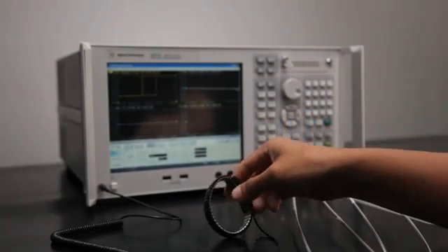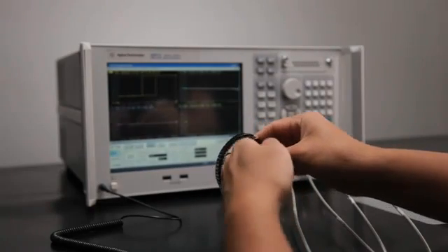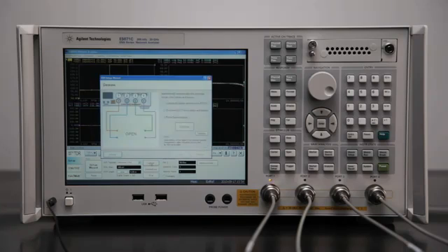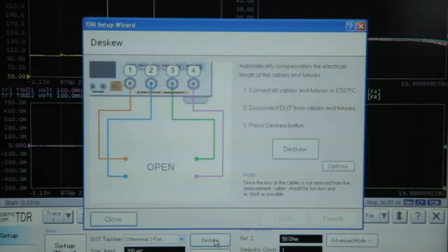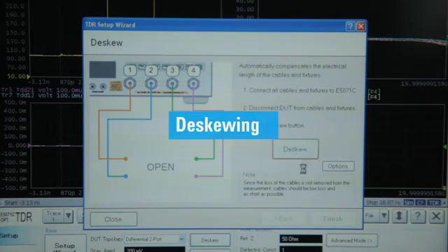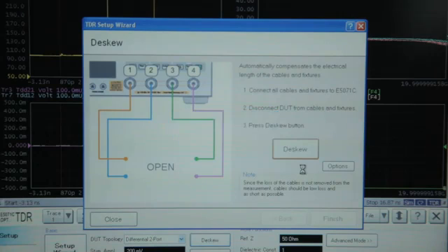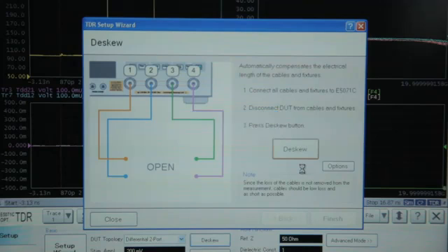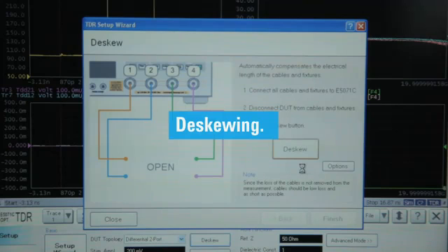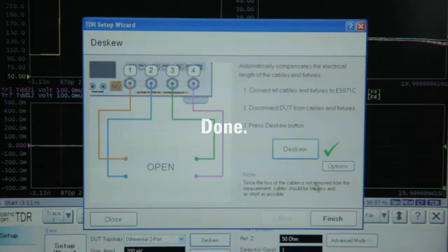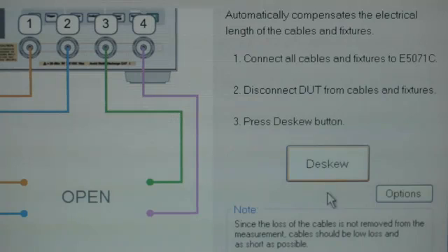Compare this to ENA Option TDR. When you first come in contact with the instrument, you may think that you were missing something. Why, the procedure for deskew can be done with one click. All troublesome settings are taken care of automatically by ENA Option TDR. In the time it's taken me to explain the procedure, our deskew is already done.